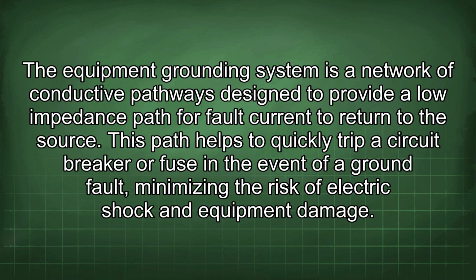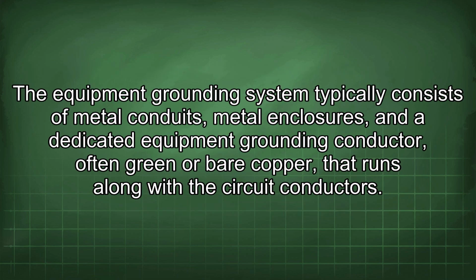The equipment grounding system is a network of conductive pathways designed to provide a low impedance path for fault current to return to the source. This path helps to quickly trip a circuit breaker or fuse in the event of a ground fault, minimizing the risk of electric shock and equipment damage. The equipment grounding system typically consists of metal conduits, metal enclosures, and a dedicated equipment grounding conductor, often green or bare copper, that runs along with the circuit conductors.